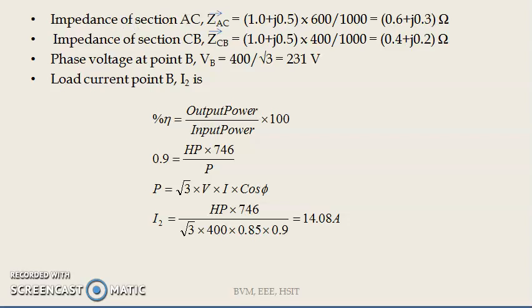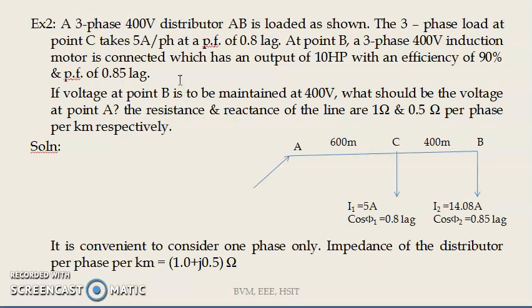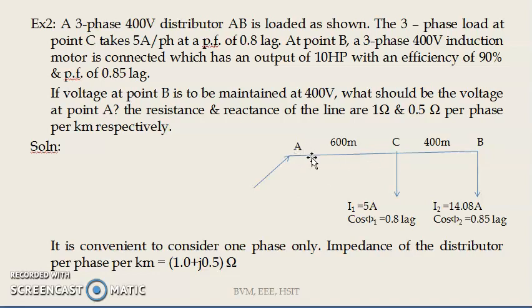What has been asked is: if the voltage at point B is to be maintained at 400 volts, what should be the voltage at point A — that is the sending end voltage. To calculate the voltage at point A, you must know the voltage at point C, and add the voltage drop in section AC to it. So you add the voltage drop in section CB to VB to get VC, and then add the voltage drop in section AC to VC to get VA.